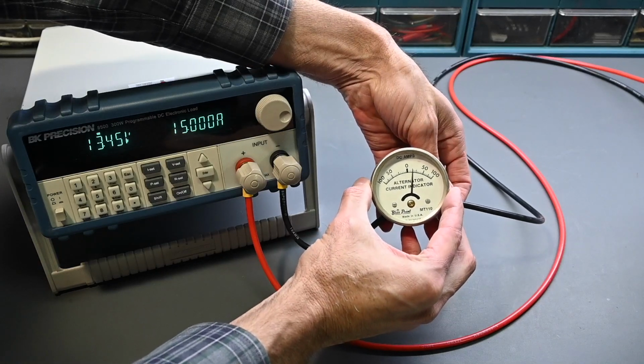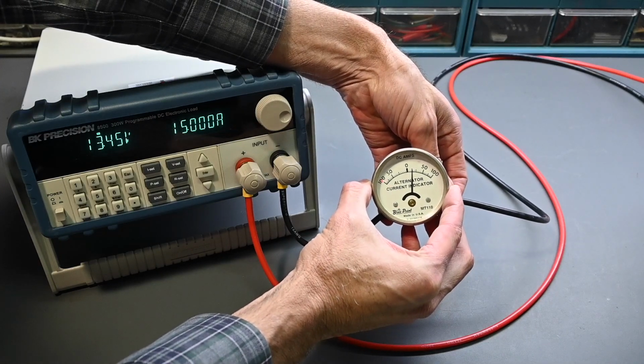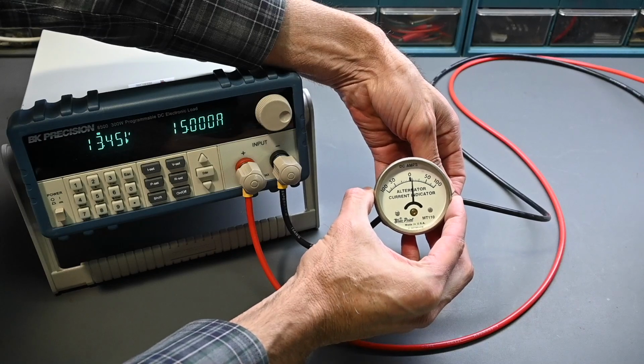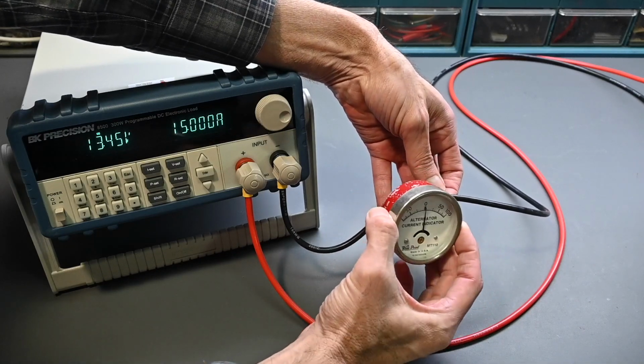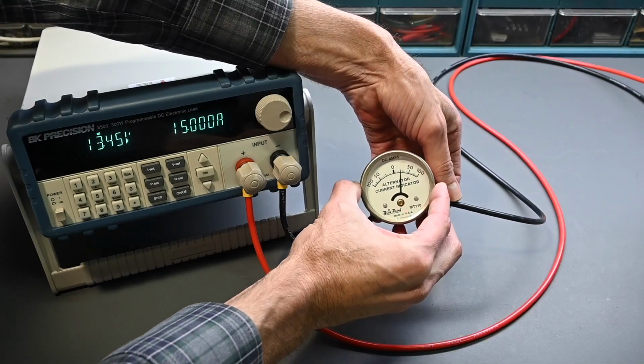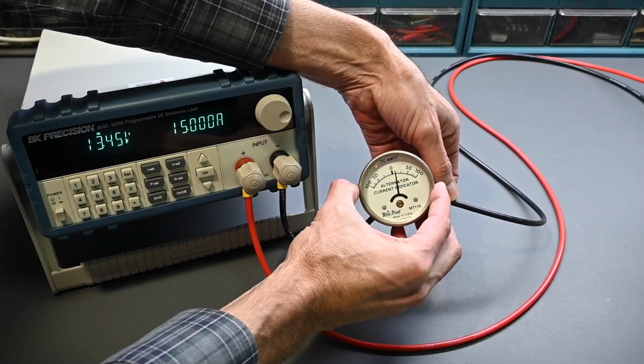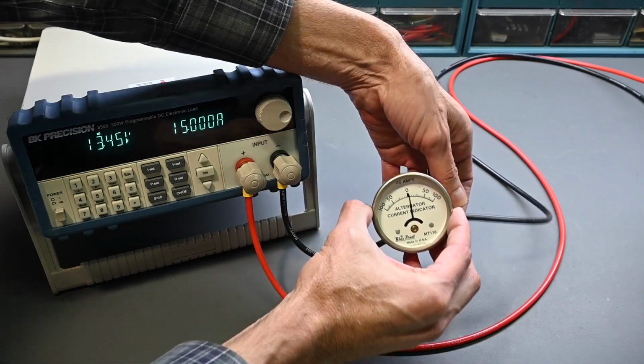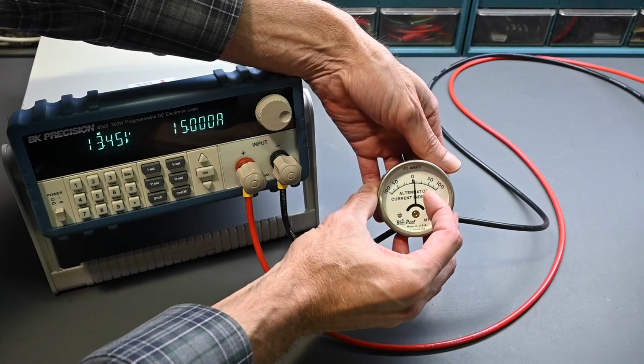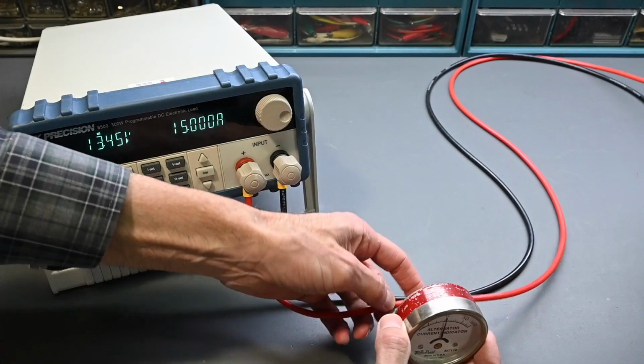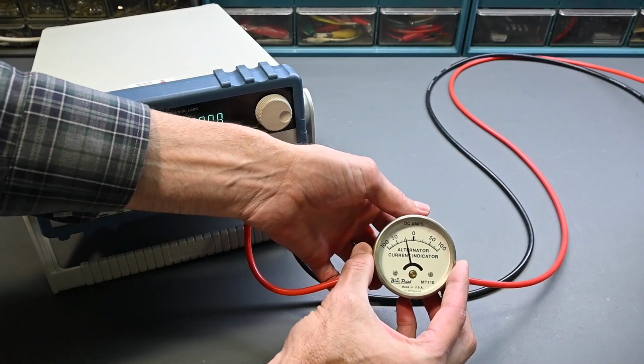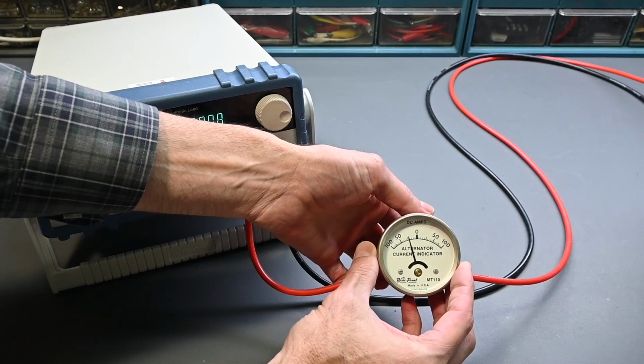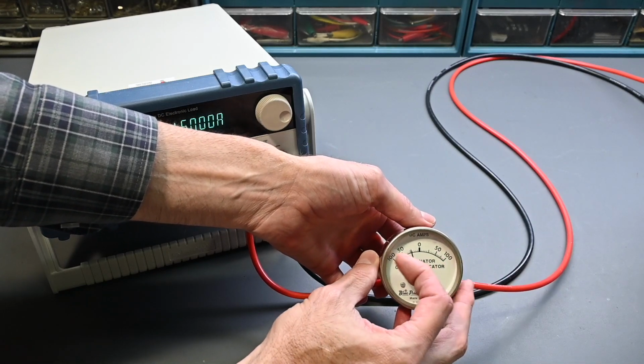But it doesn't take much distance away from the wire. You know, as I start to move that, see how the needle goes back towards 0? So imagine if this wire had very thick insulation on it. Effectively, that's moving it out away, and it does affect the accuracy quite a bit. Now notice it's deflecting to the right-hand side. If I go to the other positive wire right there, you can see it moves over to the left-hand side. So that's why the scale goes both directions.